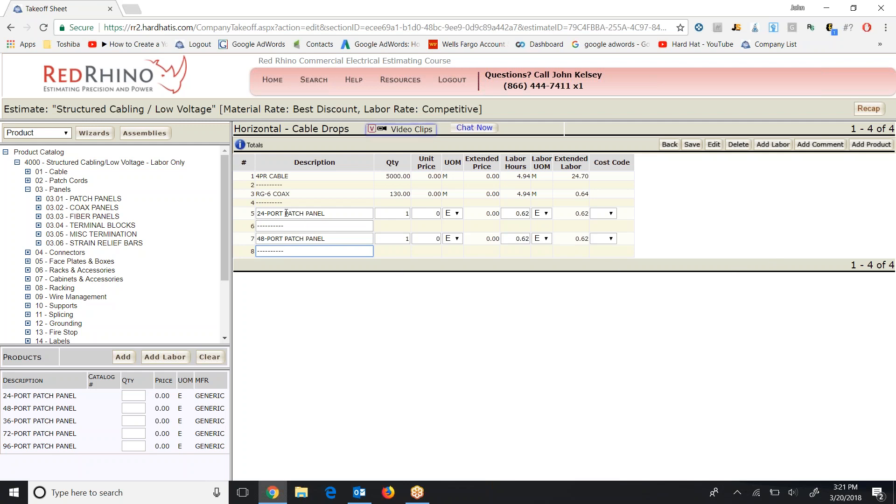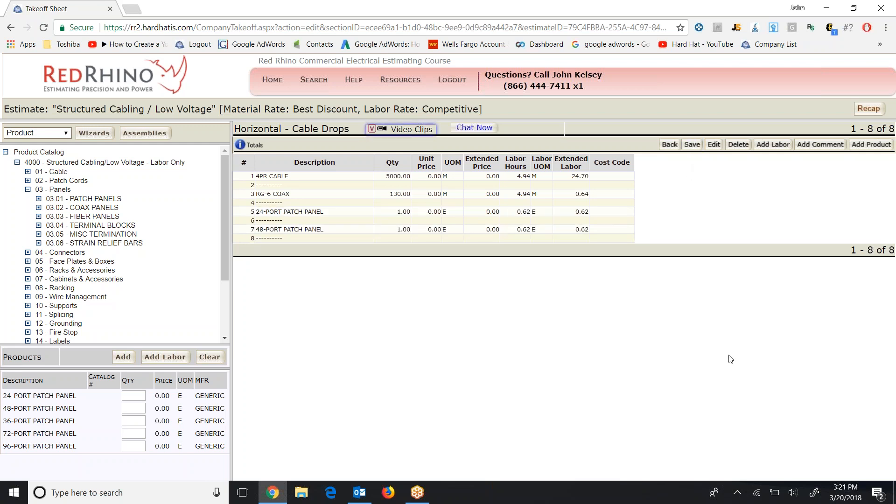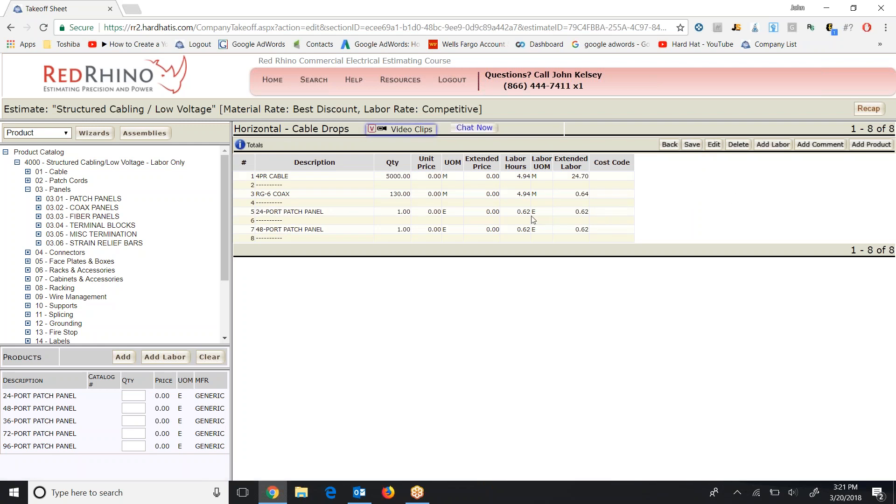Now again, for patch panels, it doesn't include terminations or anything. It's just mounting a patch panel, and it shows 0.62 hours. Let me save my work first. I'll click save here. And then we see it shows the, again, description quantity. This is per each on this item here. It's per each. So it shows 0.62 hours each, which is about a little bit over half an hour. Something else I want to throw out here just real quick. Red Rhino inputs labor in hundredths of an hour, and it displays in decimal form for more accuracy. So 0.62 represents 0.62 of an hour.